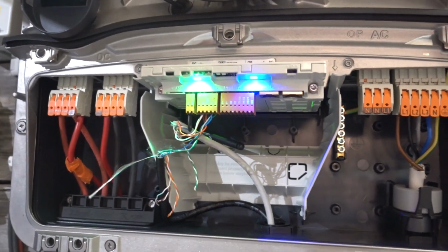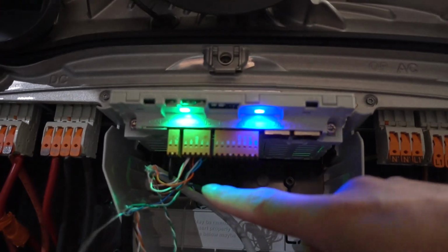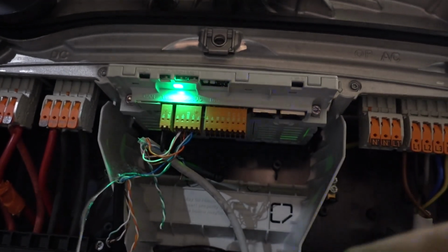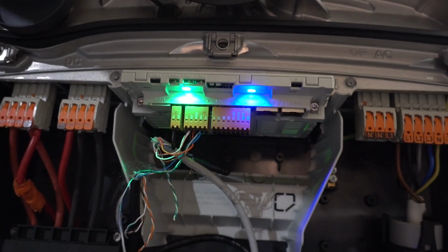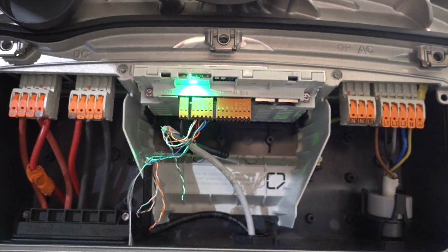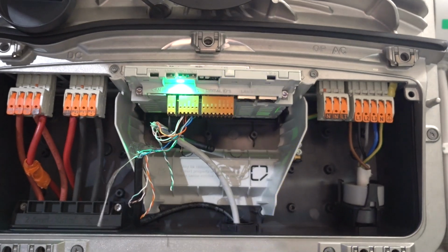So the issue was actually here. One of these cables came loose, so while we were wiggling it, we could feel that, yeah, it just slid right out. So the communication line was broken. But once that was reapplied, everything just started to work.